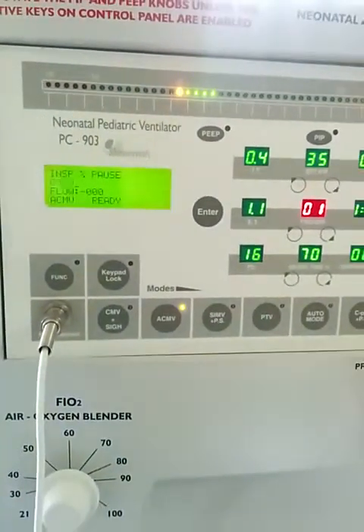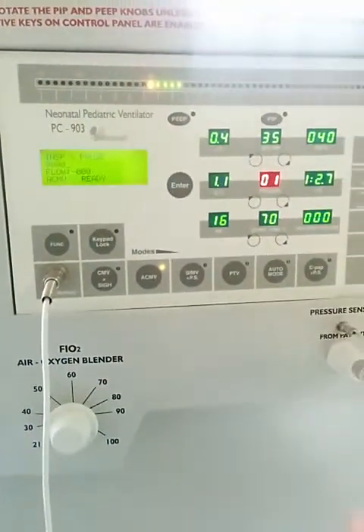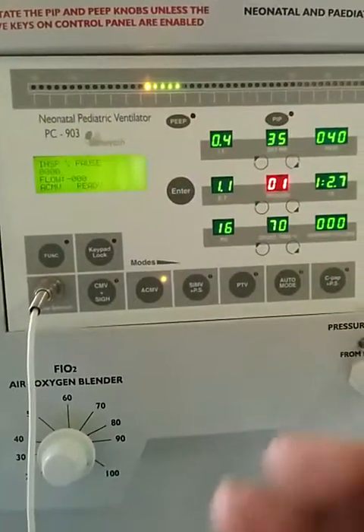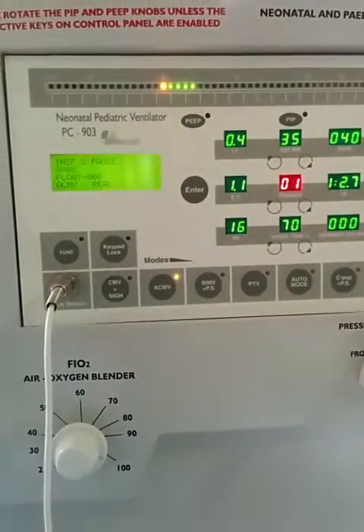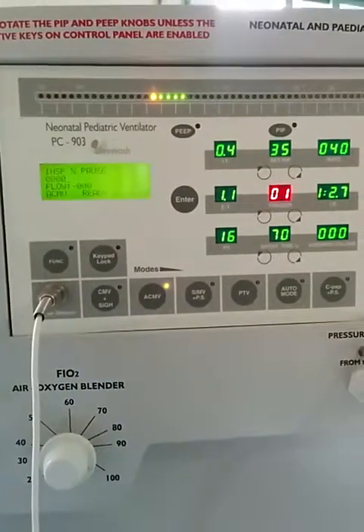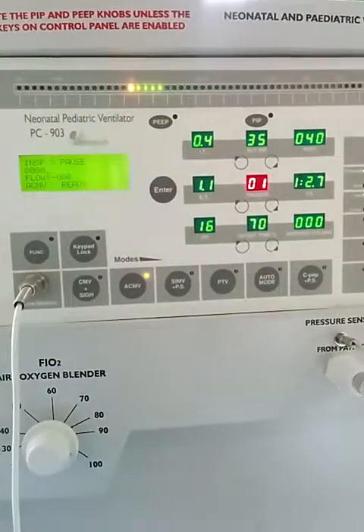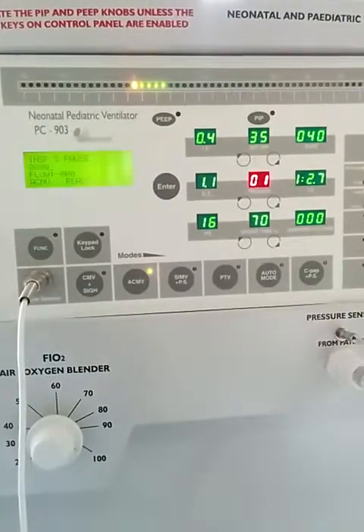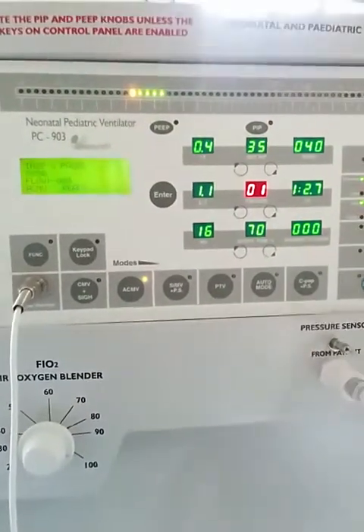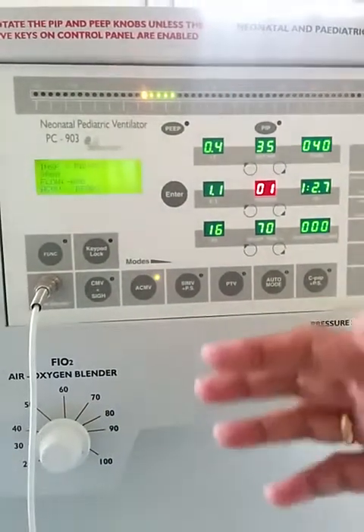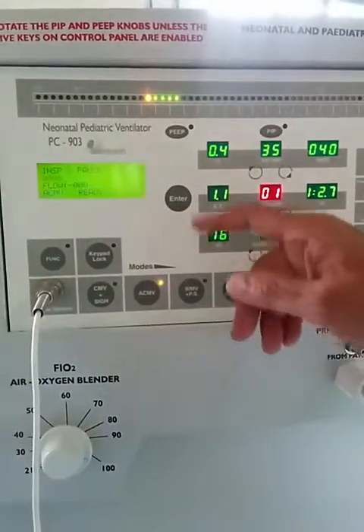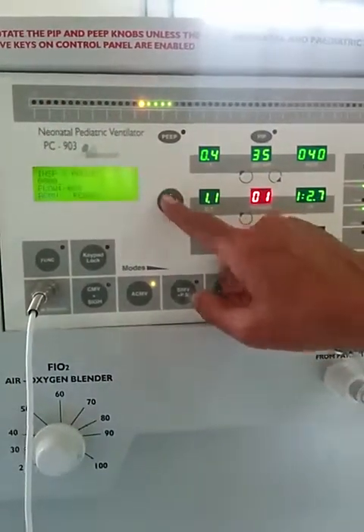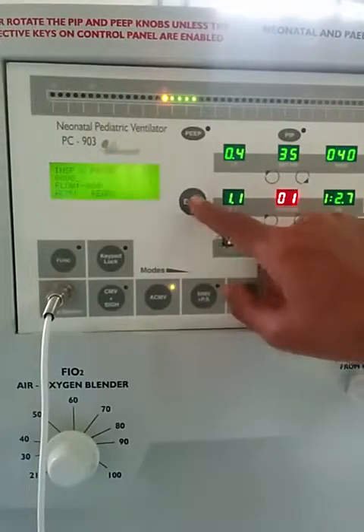Normally the setting ranges from 0 to 30% of the inspiration time, which simply means that if you have an inspiration time of 1 second and you set an inspiratory pause of 30%, then after the inspiration, the expiration will not be allowed up to 1.3 seconds. But normally nowadays we don't use it. That's why we are not setting that. So I just skip this and I press enter.